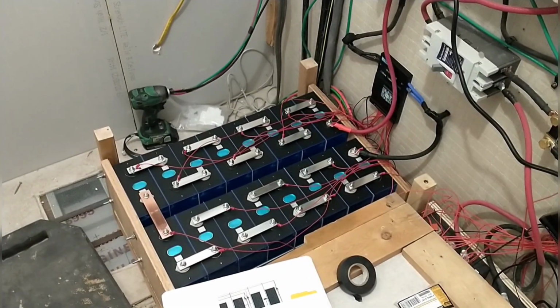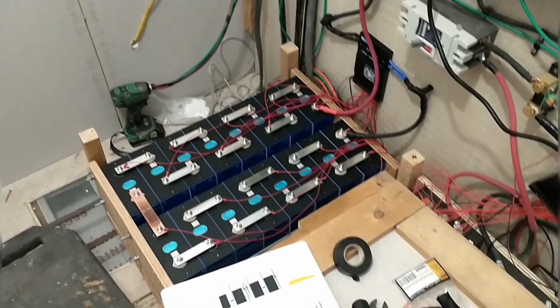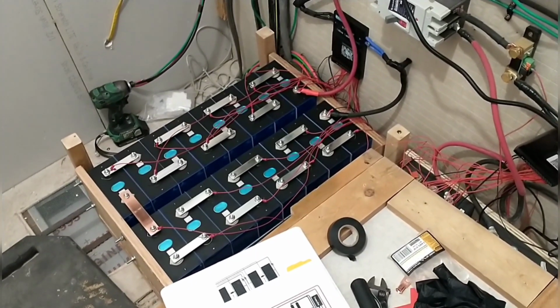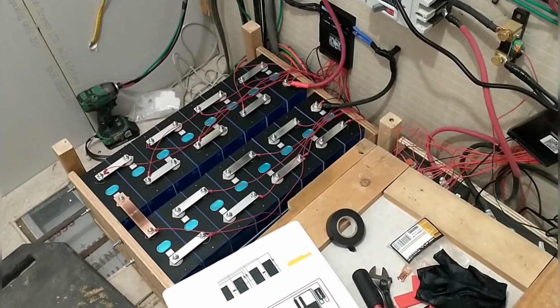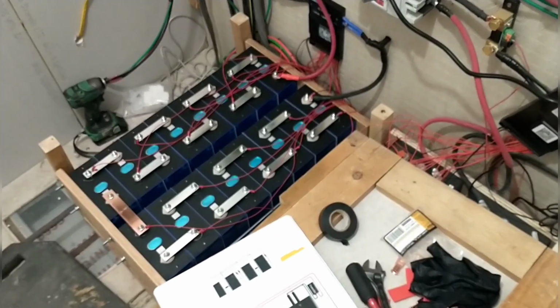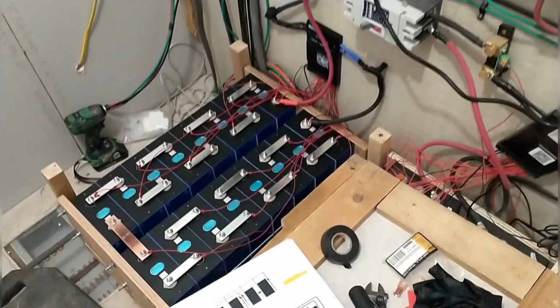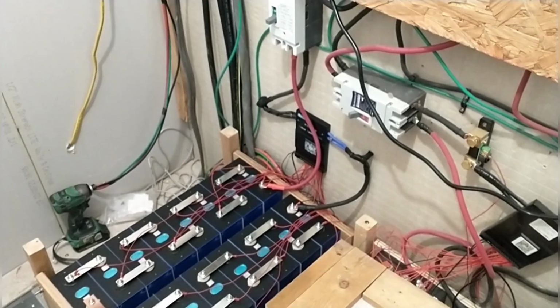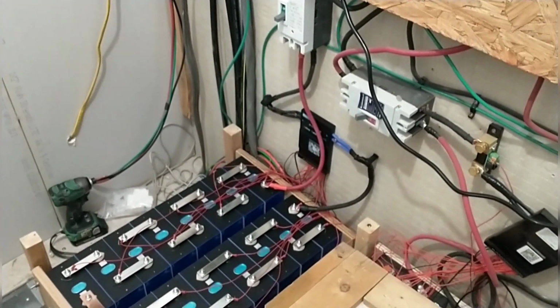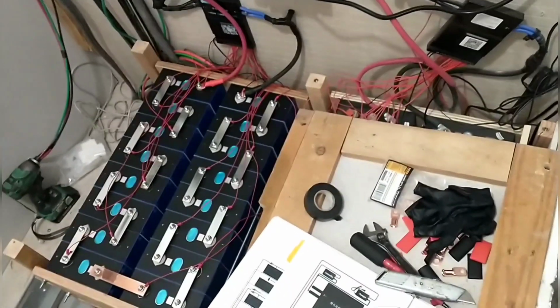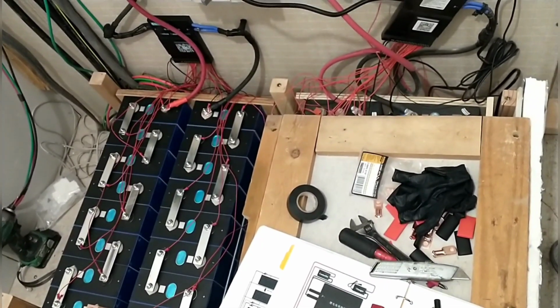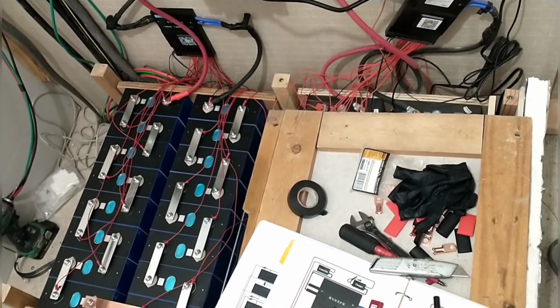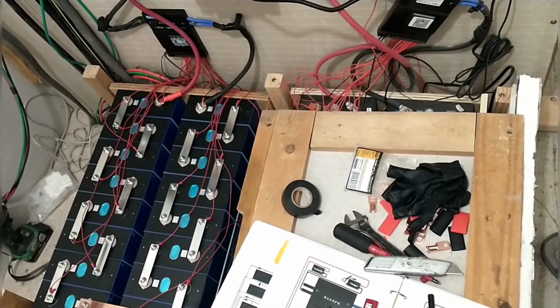I have the second battery all built and ready to go. It's connected to the BMS, all the little wires connected, and that's connected to its own breaker, but I haven't connected the breaker yet, so it's still totally separated from the system. At this point I'm ready to check the voltage on this battery, then check the voltage on my current in-service battery, compare the two, and see how close they are. I need to get them within half a volt before I can connect them together.